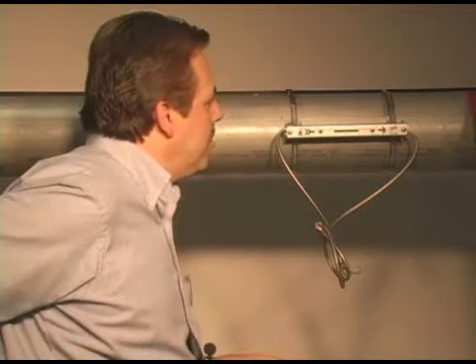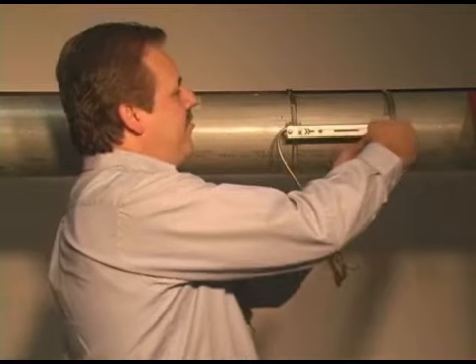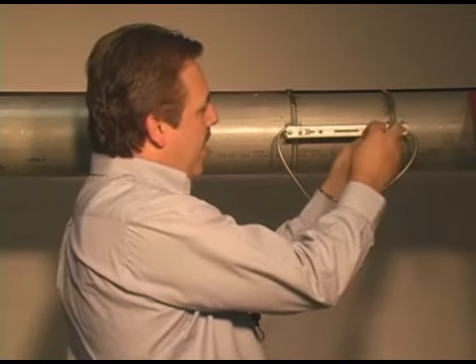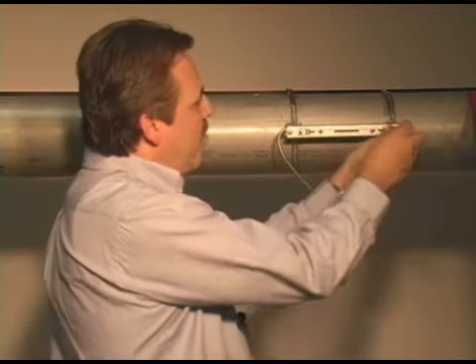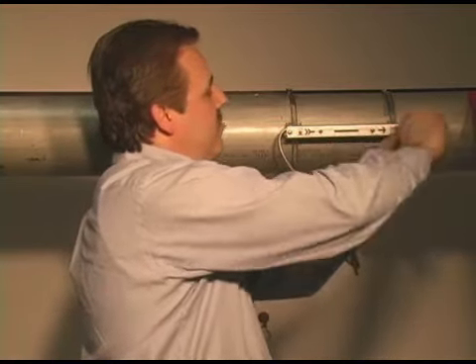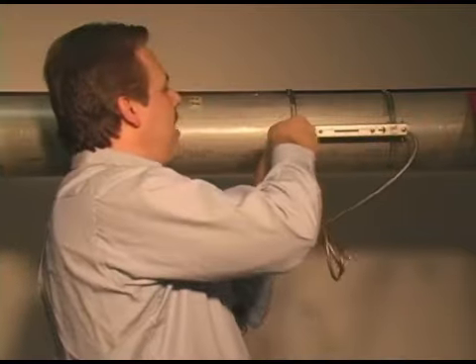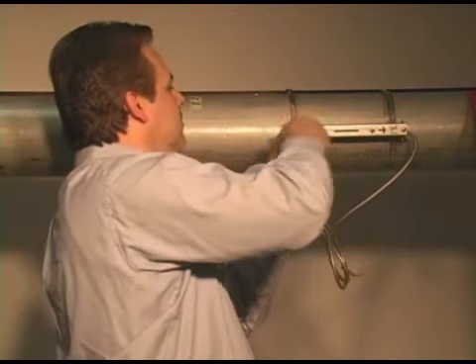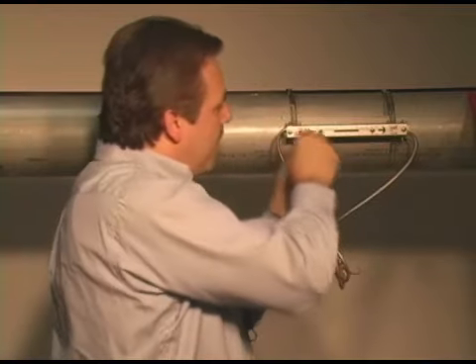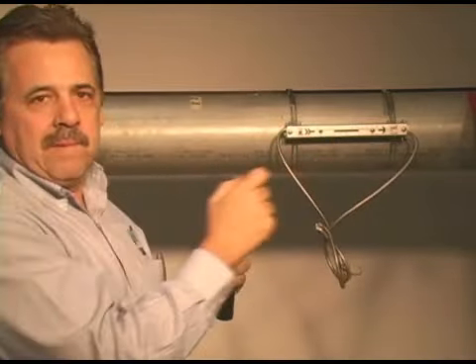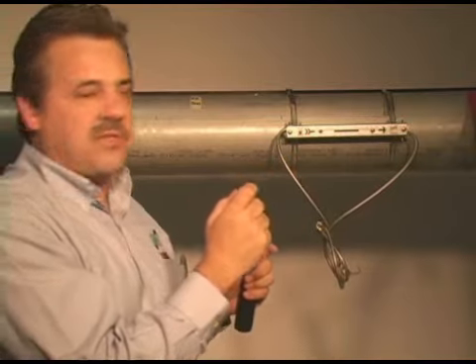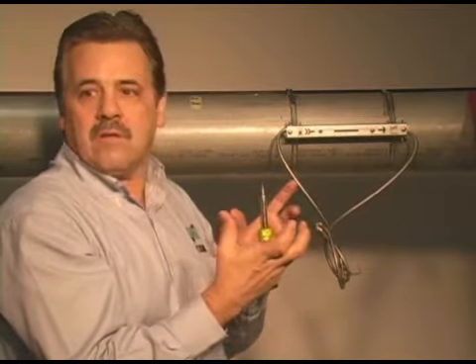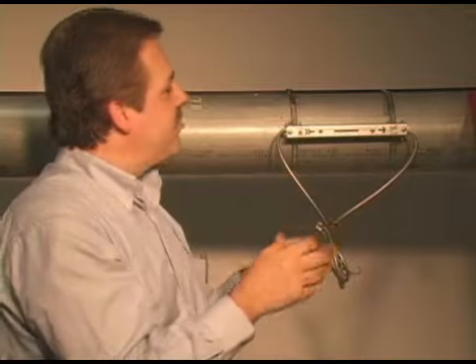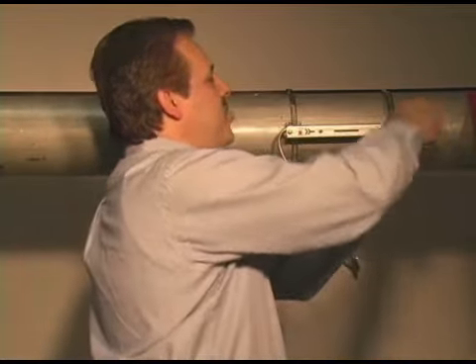Okay, so if you find out that you have to adjust the spacing, one of the reasons for that might be to peak out the signal amplitude. You would loosen up on one of these guys. You can slide it over. Probably going to have to loosen up on the outer screw as well. So we have to loosen up on both of them. You would slide it over, and you want to keep your eye on that coupling pad and make sure it stays underneath the transducer. If you have to pull it all off again to reposition the spacing, then do so, and then tighten it all down. So that's pretty much it.